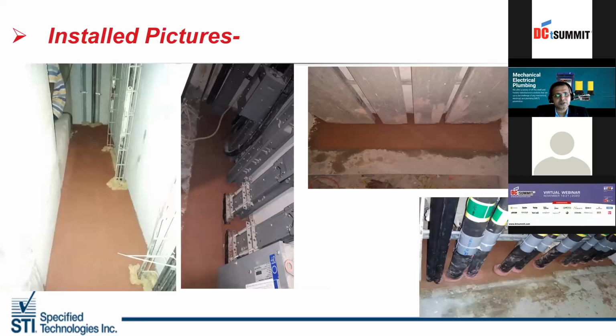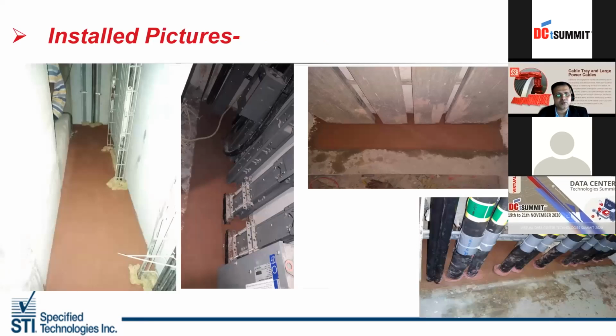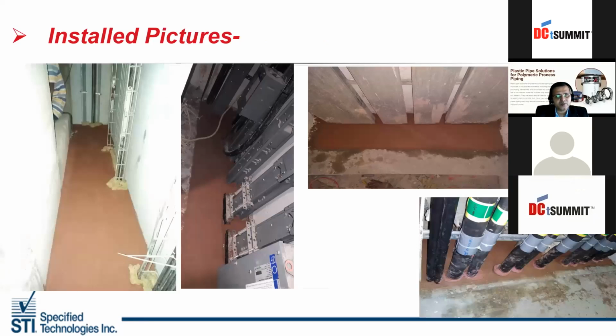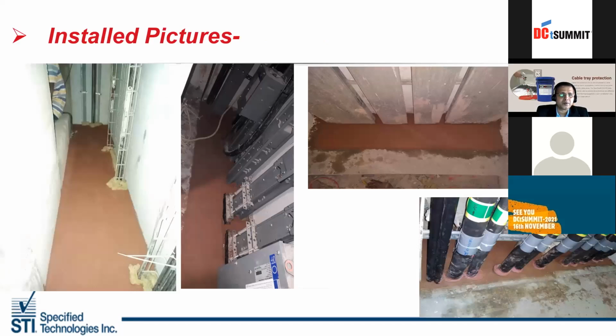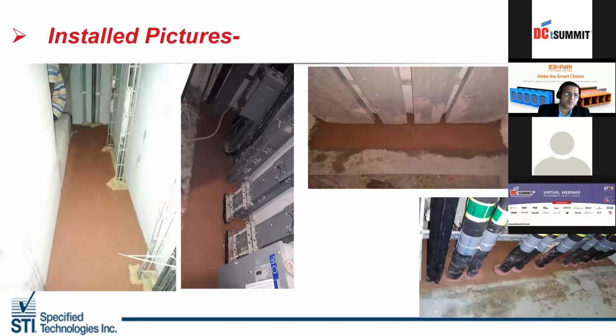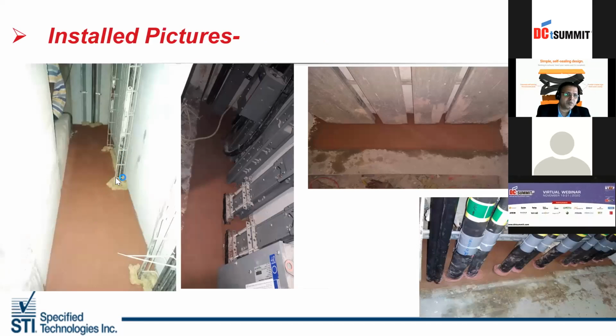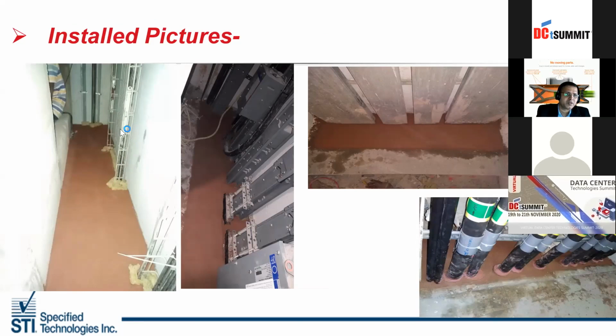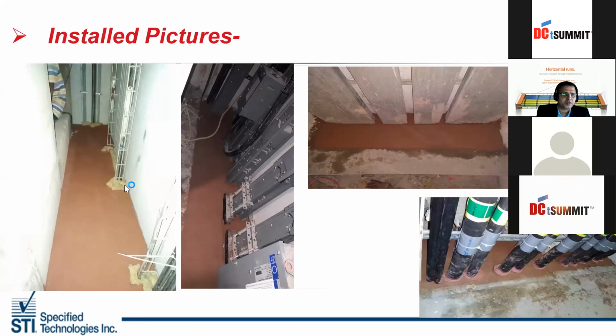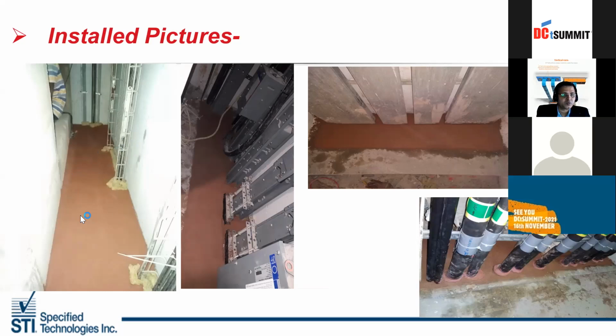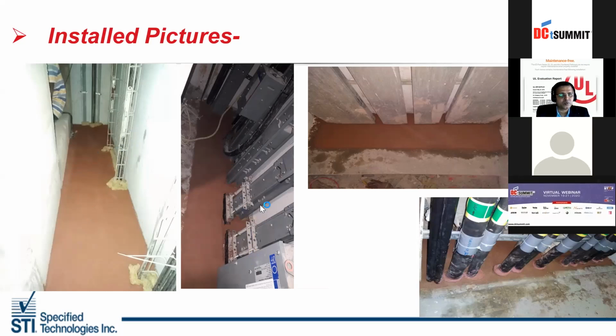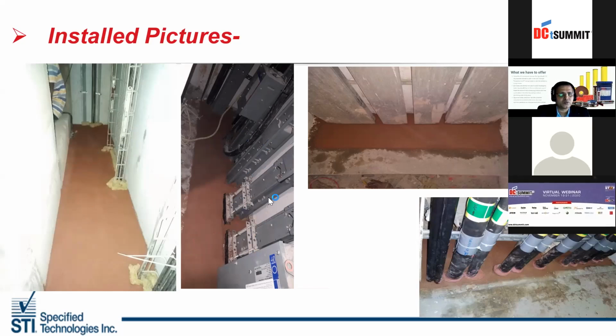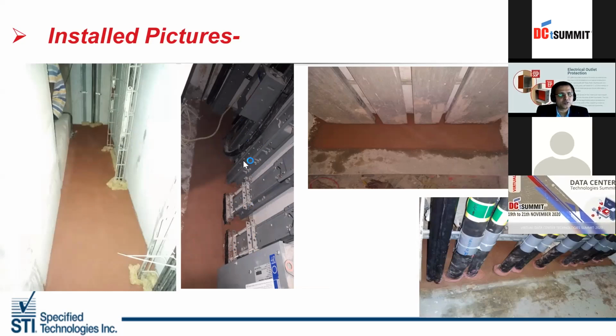So you can see the larger shaft towards your left hand side, a very big shaft, with hardly any cables and cable trays passing through the floor. So what we have done is we have installed the mortar. Mortar, as I mentioned, is used only for metallic pipes and metallic ducts. Now, in the same picture, towards the walls, the cables and cable trays are passing. So we have to use two products here in combination for these scenarios: mortar plus the intumescent sealant. In the center, you can see the bus bar passing through the floor. One single product, the mortar, is used because it is a metallic product.